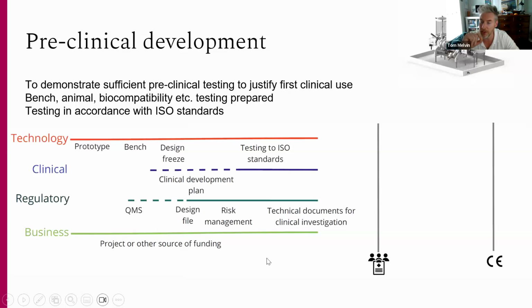Once you make the decision that you have a prototype that's worthy of further development, this is really when you get into formal product development, and you're going to have to start thinking about regulatory compliance in a more organized way. So when you move from design freeze into further preclinical development, you'll be mapping out what are the standards that apply to my device, because this will inform some of your bench testing or maybe your toxicology or biocompatibility test requirements. So you'll have to map these out and plan your testing strategy.